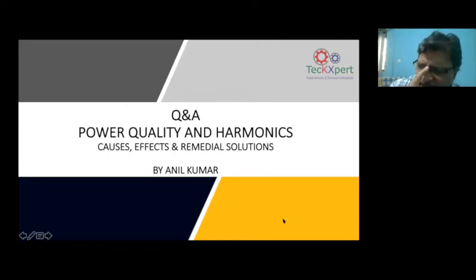Coming back to this question, we can always compute and say what is the extent of impact on the grounding in a given network due to harmonics and higher frequency current. We can compute and tell you this is the impact. The financial saving, of course, the only thing is you have to then improve the grounding and reduce it. The cost of that can sometimes be very high, because you need to look at whether there are implications in terms of bearing failures and all that. Yes, the answer to that question is yes, we can determine what is the impact on the ground and accordingly tell you what improvement you need to do on the grounding. That we can recommend.